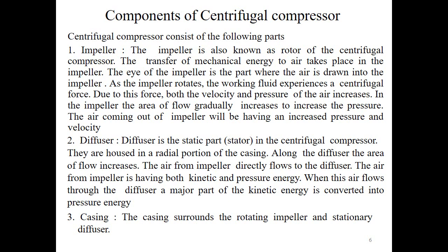Now the second component of the centrifugal compressor is the diffuser. It is a static part, also called the stator in the centrifugal compressor. They are housed in a radial portion of the casing. Along the diffuser, the area of flow increases, so that as the flow area increases, the velocity comes down and pressure increases. Now the air from the impeller directly flows to the diffuser.